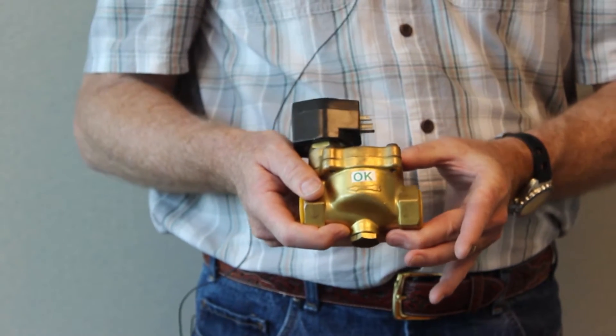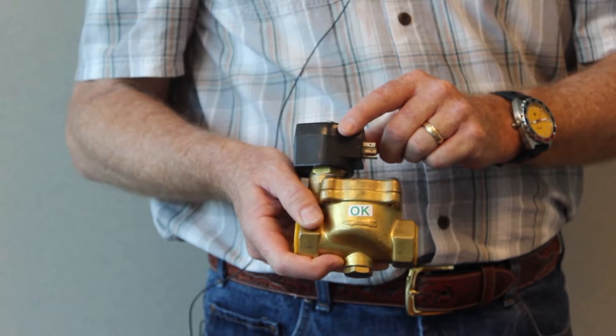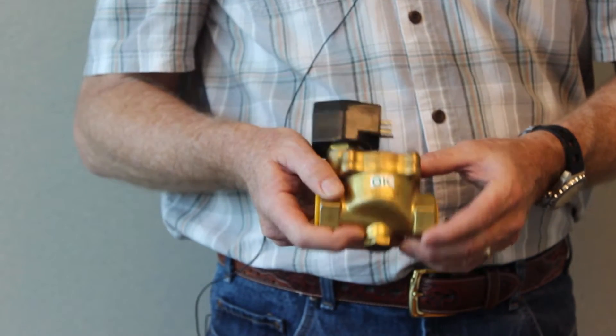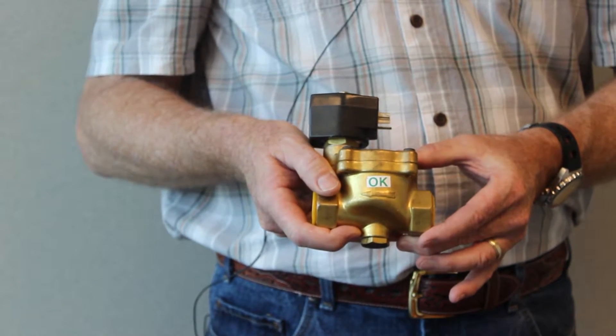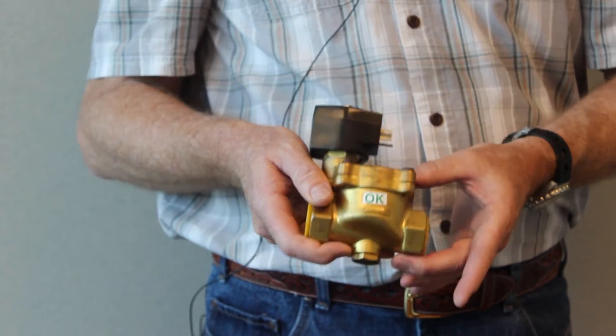If you do not have enough water pressure and you energize the solenoid, it will not open. If you have too much water pressure and you de-energize the solenoid, it may not close.